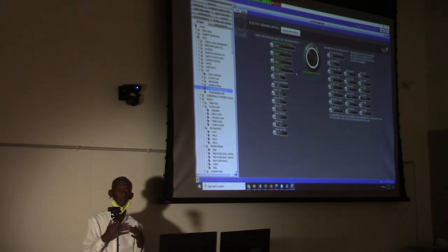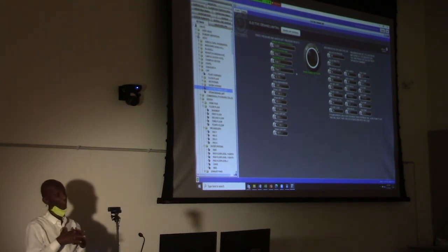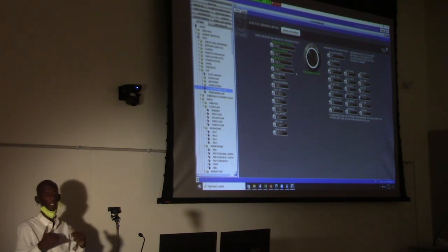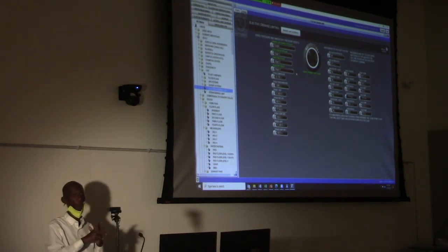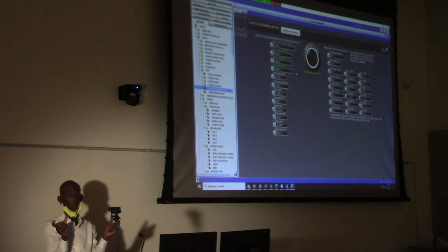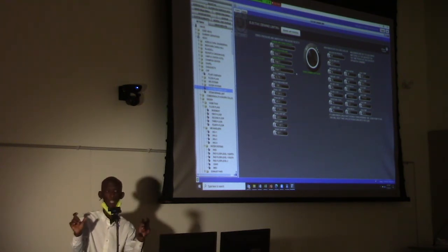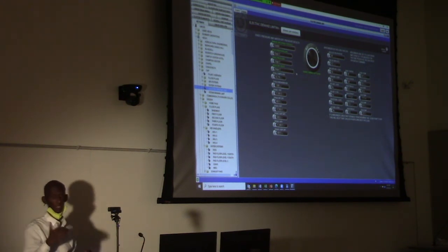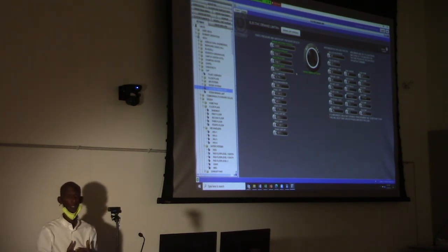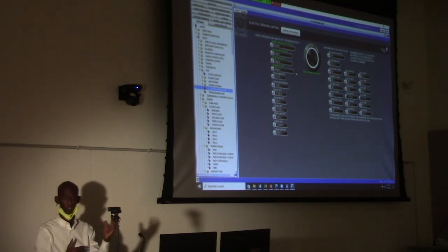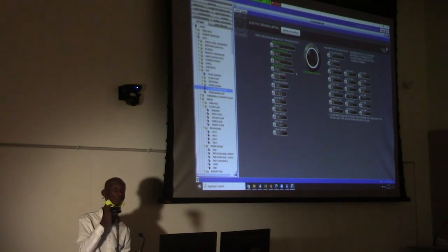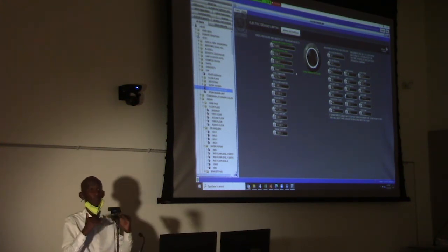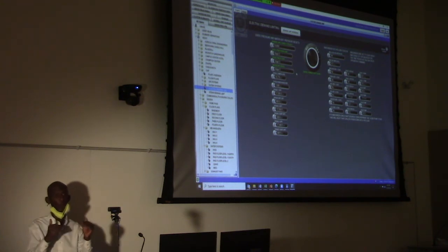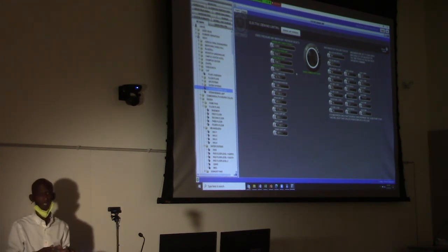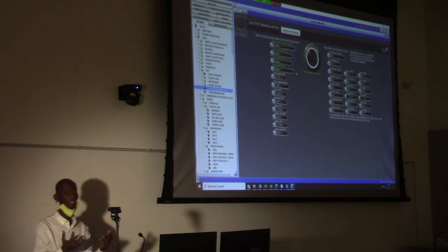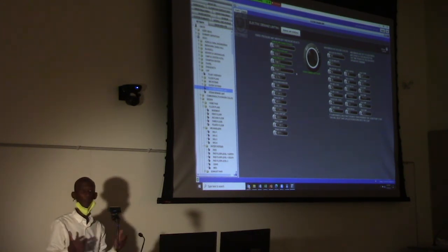But when you set back the temperature, we didn't even have enough people here. We had just the essential people, and they were very limited in number, probably 1 or 2 trades only per day. So what happened remotely, we set back the temperature in the spaces, and we did monitor the temperature. But we didn't want to turn off everything, because if you turn off everything, guess what? You may freeze a coil and nobody is around. And when nobody is around, if you freeze a coil, water keeps coming and you may flood the whole building.